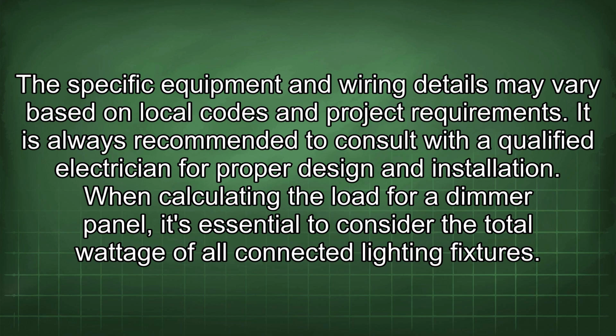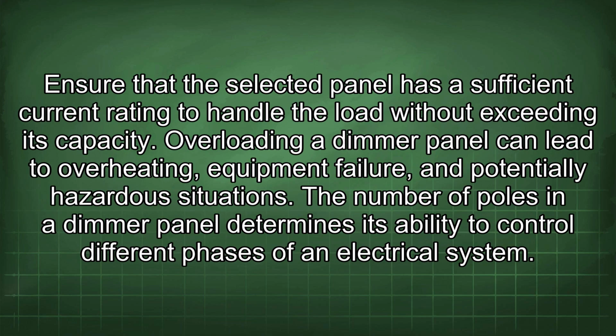When calculating the load for a dimmer panel, it's essential to consider the total wattage of all connected lighting fixtures. Ensure that the selected panel has a sufficient current rating to handle the load without exceeding its capacity. Overloading a dimmer panel can lead to overheating, equipment failure, and potentially hazardous situations.